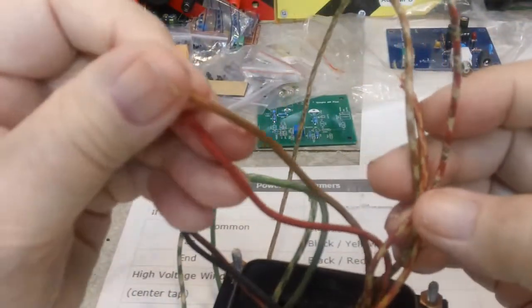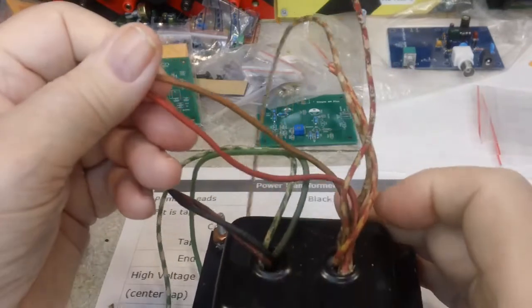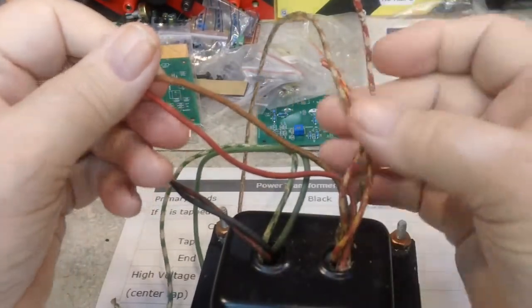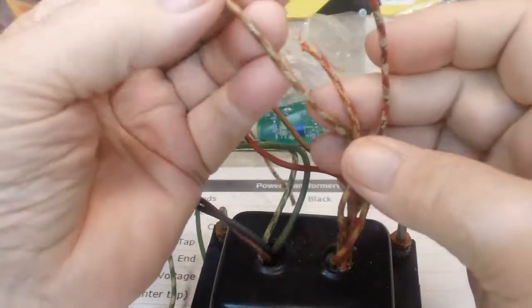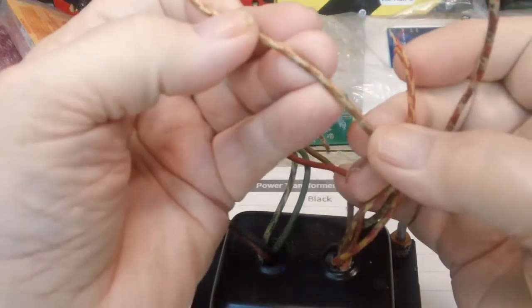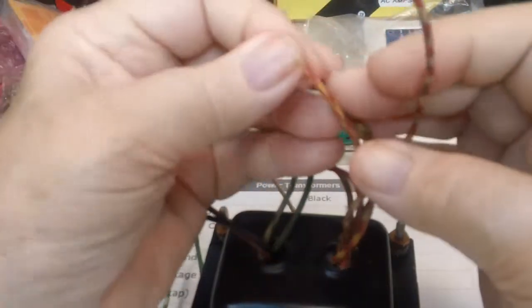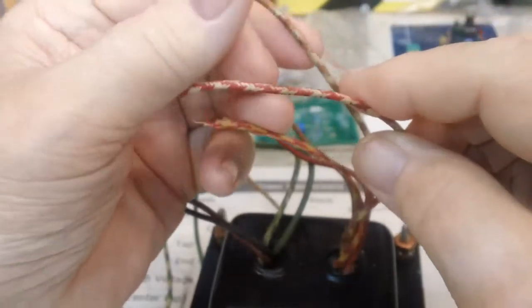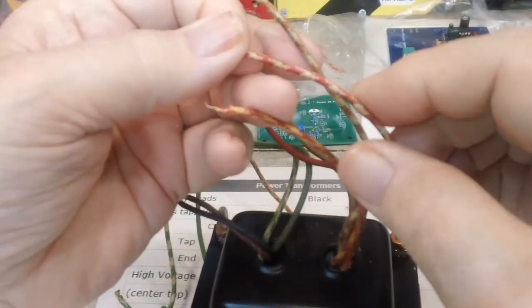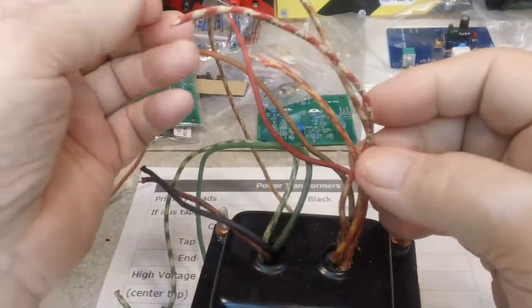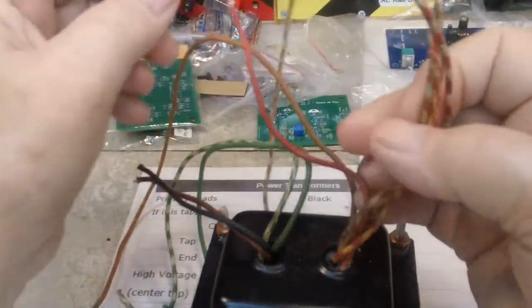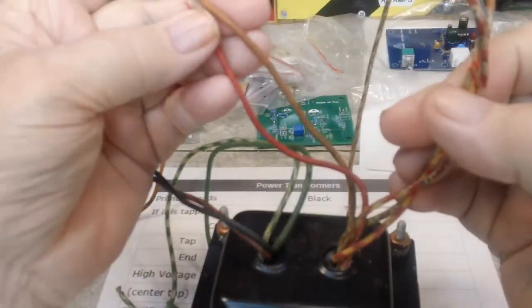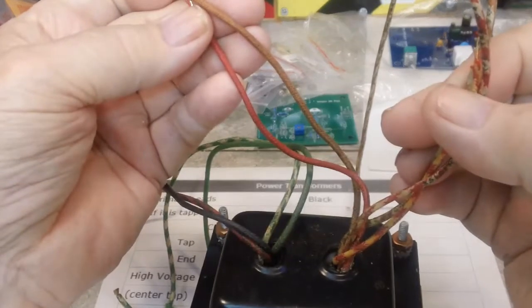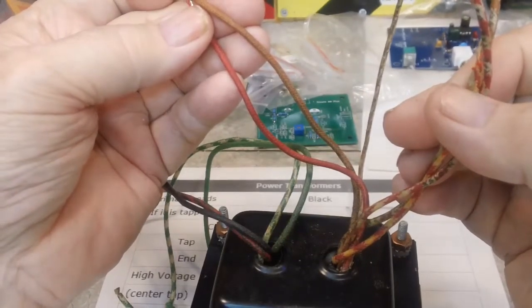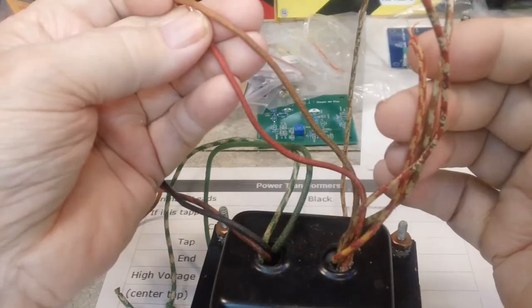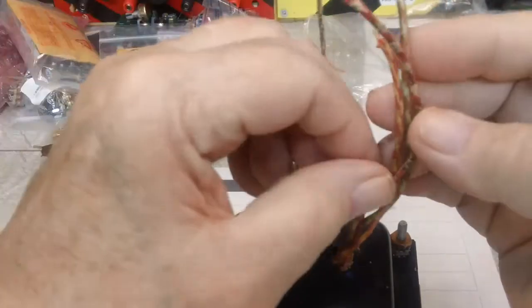Also on this, coming out of this hole, I don't know if you can see that, are three more wires. One is what I'm going to call brown and yellow, the other is red and yellow, and the other is also red and yellow. So my guess is these two are filaments - it's supposed to have two filament leads coming out of this transformer - and I'm going to say this is the center tap for the high voltage.